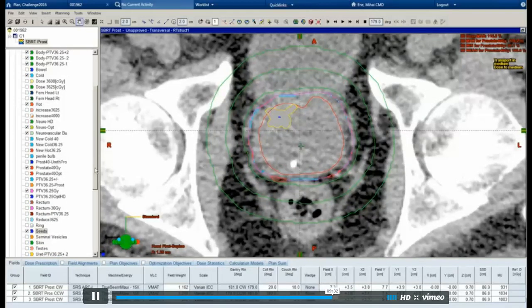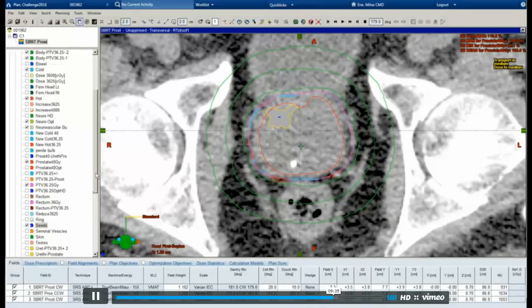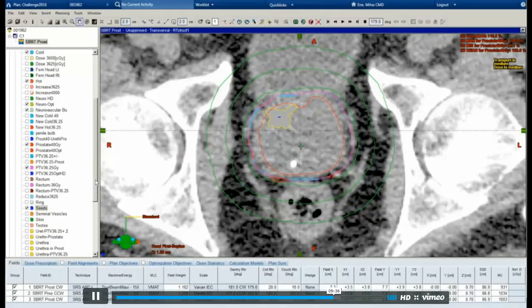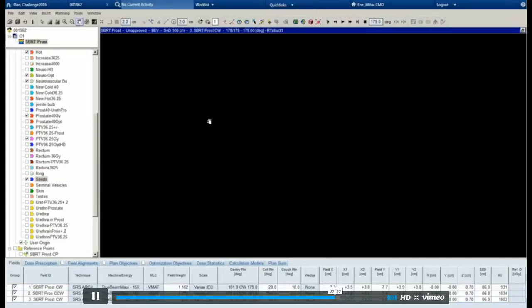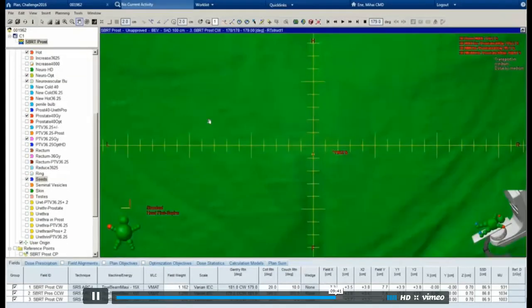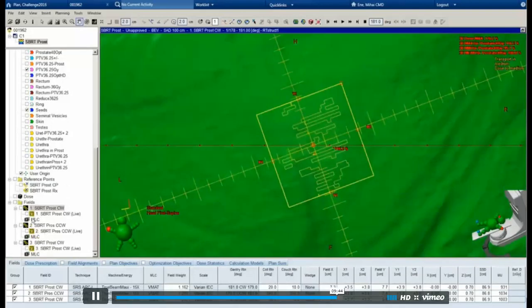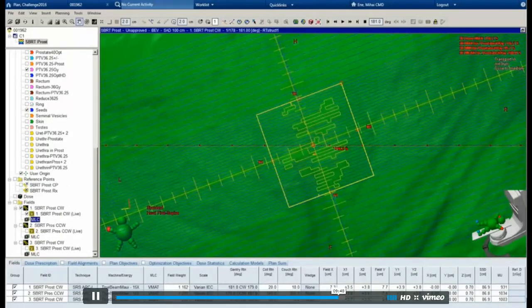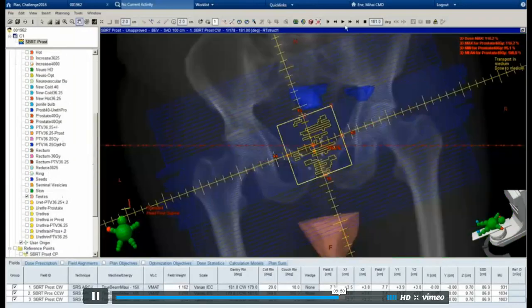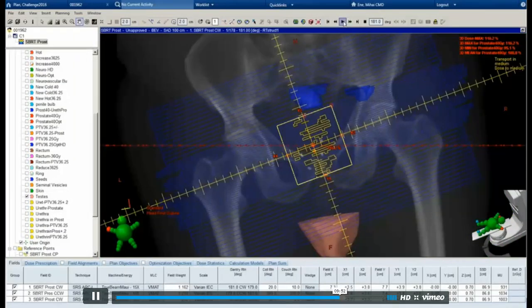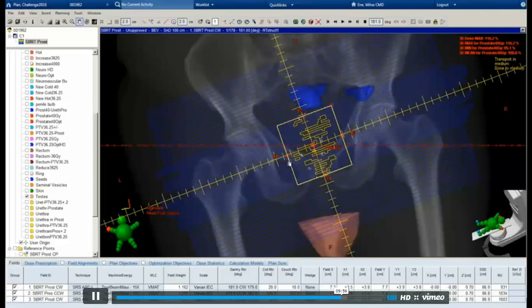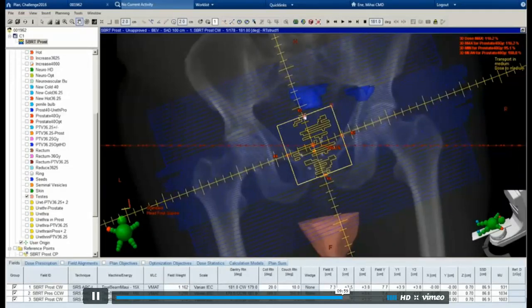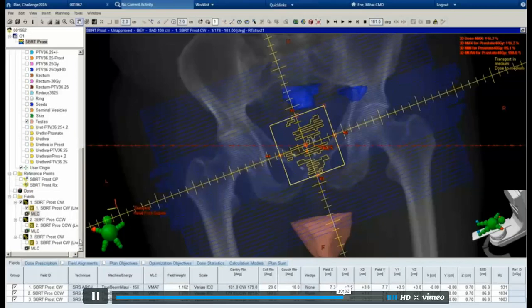Yeah, sometimes you've got to do your actual work. I'm curious, we were thinking about changing the leaf park position to a different position than what our default is. Our default is for the park leaves to meet in the center, and we thought maybe that was contributing to small leakage to testes and bowel. Our thought was to have the leaves park outside the field somewhere, the ones that aren't being used.